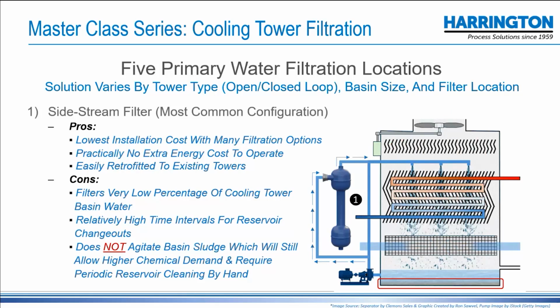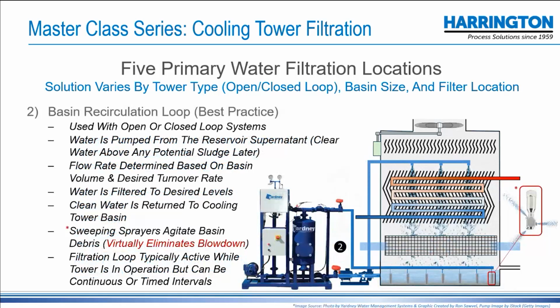Another thing is that except for the action of water falling on the surface of the basin water, it's not agitating the sludge. It's not mixing up the sludge. So it's still collecting at the basin. You still have to open a valve and drain it. The best solution, it's not the last, but it's the best, is an actual recirculation loop where you have a pump drawing water through a filter that is then being filtered and returning to the basin. And so the basin water is what's being filtered, not the water that's coming down eventually through the dispersal nozzles.